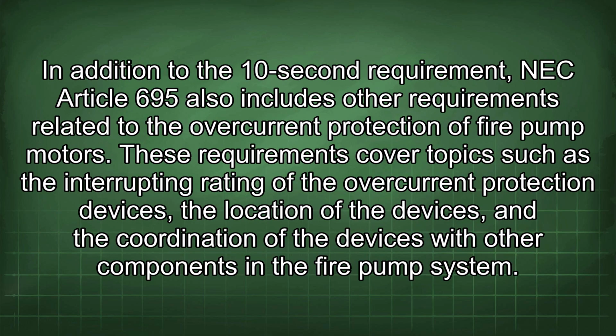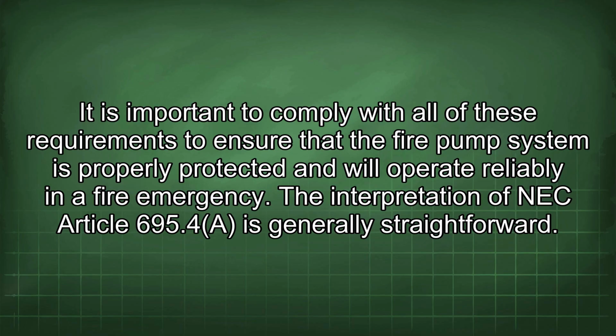In addition to the 10-second requirement, NEC Article 695 also includes other requirements related to the overcurrent protection of fire pump motors. These requirements cover topics such as the interrupting rating of the overcurrent protection devices, the location of the devices, and the coordination of the devices with other components in the fire pump system. It is important to comply with all of these requirements to ensure that the fire pump system is properly protected and will operate reliably in a fire emergency.